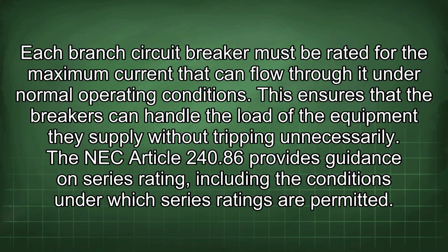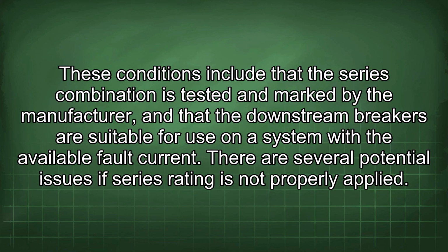The NEC Article 240.86 provides guidance on series rating, including the conditions under which series ratings are permitted. These conditions include that the series combination is tested and marked by the manufacturer, and that the downstream breakers are suitable for use on the system with the available fault current.